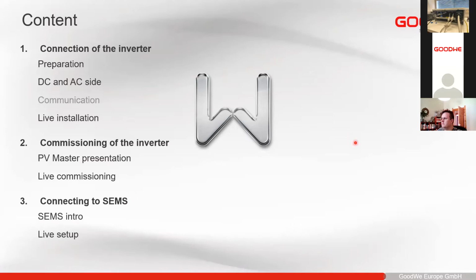So now I will shortly show the ET inverter. So here we have the ET inverter with us. Instead of any PV modules, we have a DC source here on the side. I will turn it off for now. And then here on the bottom side, you can also see the different connections. Without this, this is how it usually comes. So you have these covers here. This one is not connected, and the only thing that's different is this cable won't be here and the PV cable won't be here. So going from left to right, here you see the DC switch off and on.